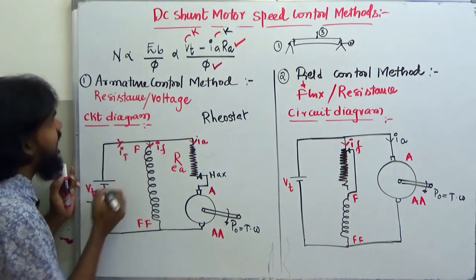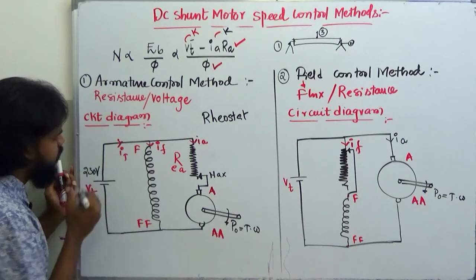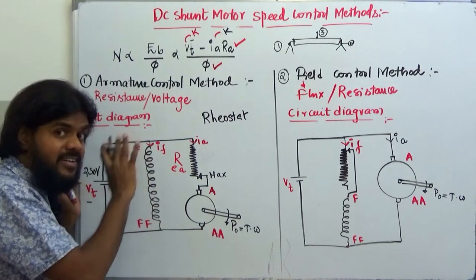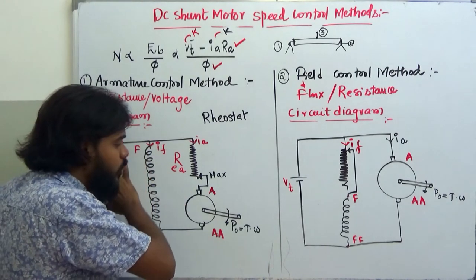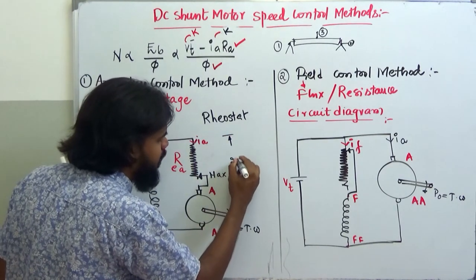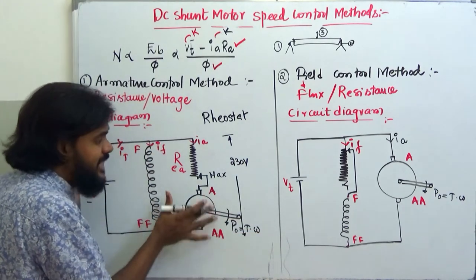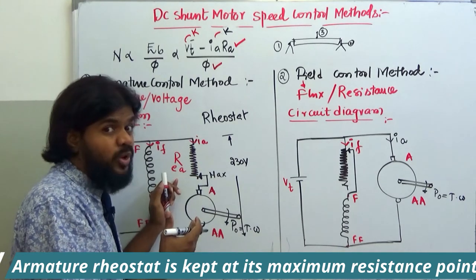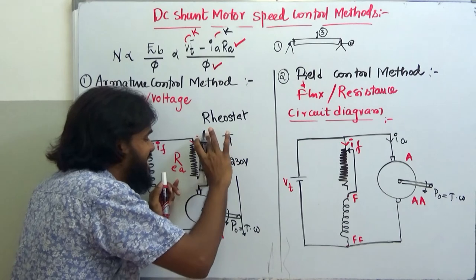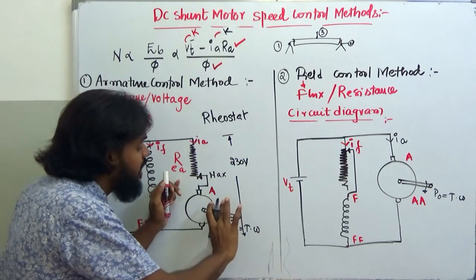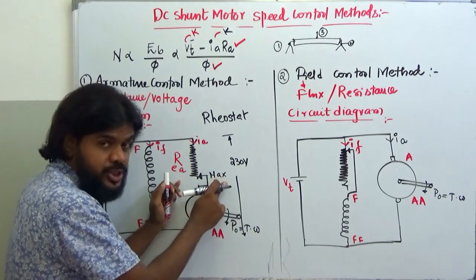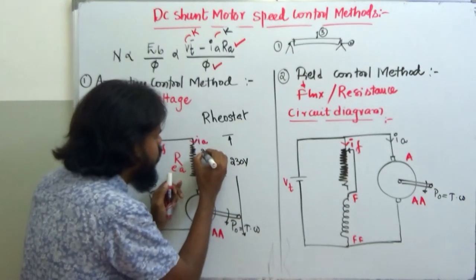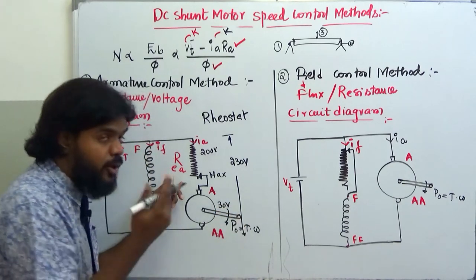Operating at rated supply voltage — say 230 V — the field flux is produced at its rated value. Since the armature rheostat is at maximum position, there is more voltage drop across the external armature resistance compared to the armature winding itself. For example, maybe 200 V drops across the external resistance and only 30 V appears across the armature.